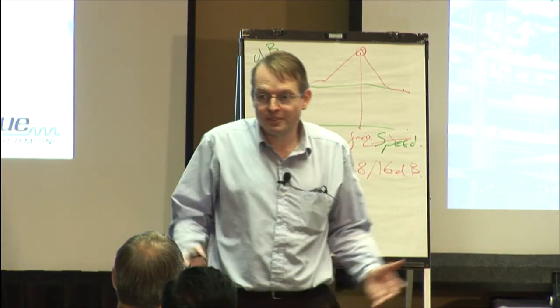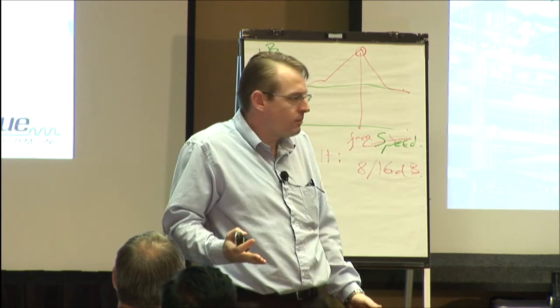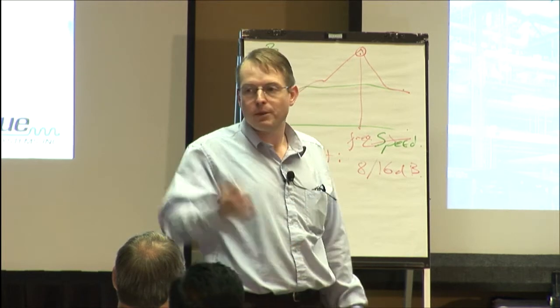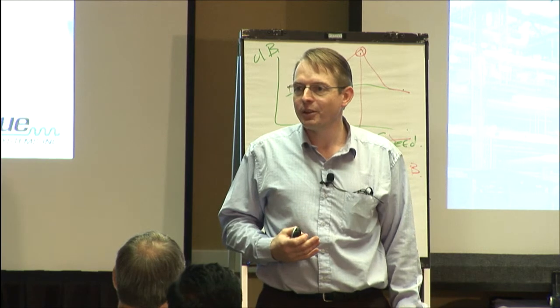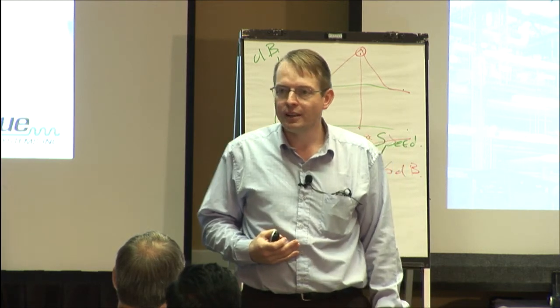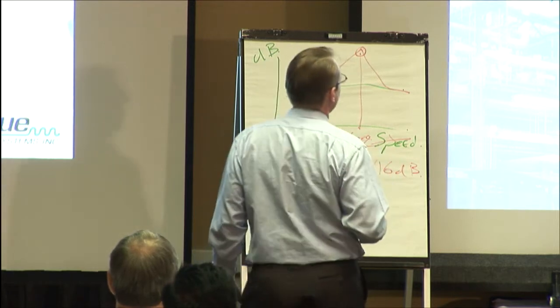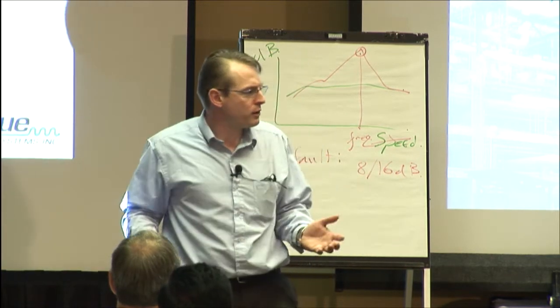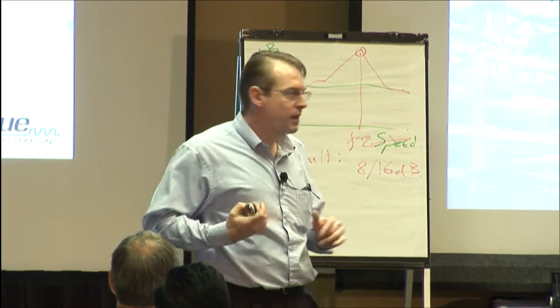Okay. Listen. Record the sound file. We're going to be able to confirm whether that's the case or not, right? Or whether it's just a raised dB. Maybe the grain's extra wet and so the load's even higher today because the grain was wet when it came in. Okay, so it's all about thinking, well, what have I got at my disposal to be able to confirm, validate, verify what I think or what I'm assuming is happening?